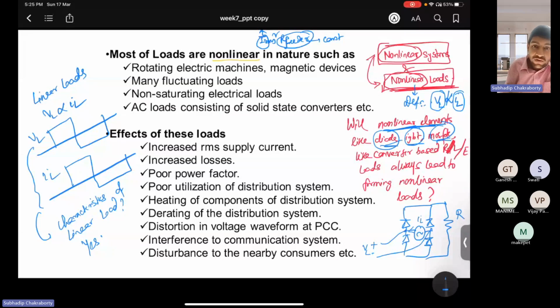So there is loss in the line for power that you are not utilizing. That means a penalty to the consumers, and it also leads to poor power factor at the AC side. So that's why it is a great concern both for the operators as well as for the consumers. So it should be prevented, both at the generating end as well as at the distribution end. The effects are, as I told you, RMS currents increase and losses, obviously poor power factor, and poor utilization, because the rating needs to be increased but the power is low.